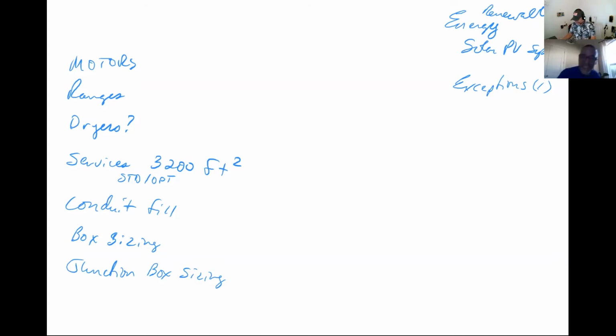Alright, so 220.54. Effectively, there's a caveat for using this table written in that article stating you cannot use the table with any value less than 5,000 watts as a minimum. If the nameplate of the dryer is higher, use the higher number, but if it's lower, you have to bump it up to that minimum threshold of 5,000 and use the table at the top of the page. So write yourself a note at the top of page 73: minimum 5,000 watts, so you don't forget.